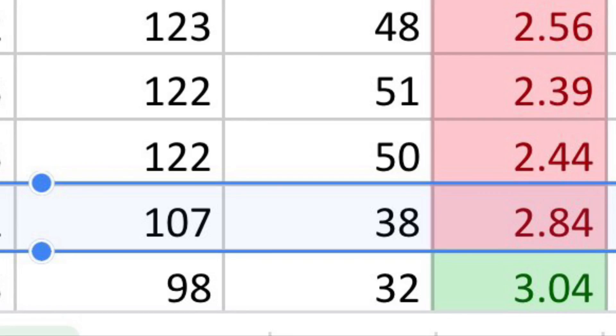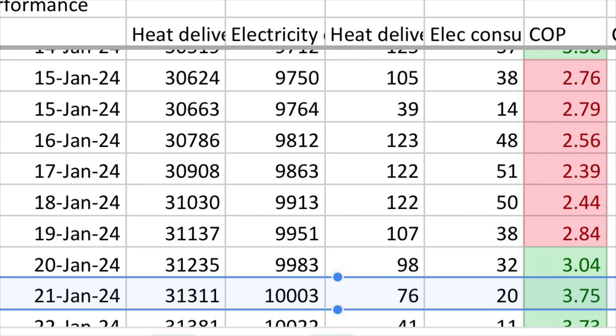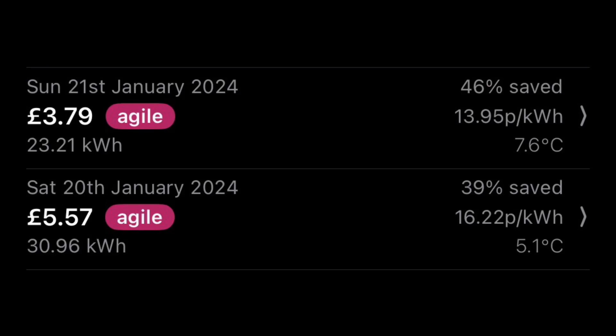I'm going to carry on briefly into Saturday and Sunday. The weather forecast was due to get milder again. On Saturday, we had an average temperature of around 5 degrees C, and Sunday, 7.6 degrees C. On Saturday, the heat pump delivered just under 100 kilowatt hours of heat and used 32 kilowatt hours of electricity — an efficiency just over 300% at a COP of 3.04. Electricity rates were 16.22 pence per kilowatt hour, so our costs were £5.57. Then on Sunday, the heat pump delivered 76 kilowatt hours and used 20 kilowatt hours of electricity, with an efficiency of 3.75. Our electricity rates on Sunday were even lower at 13.95 pence per kilowatt hour, so the heat pump cost us only £3.79 to run.